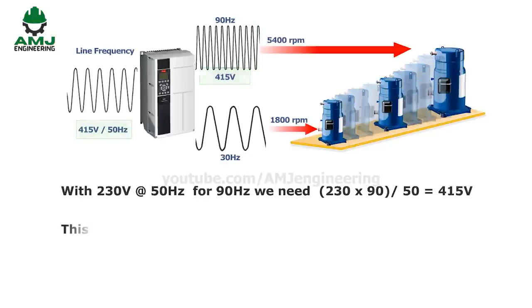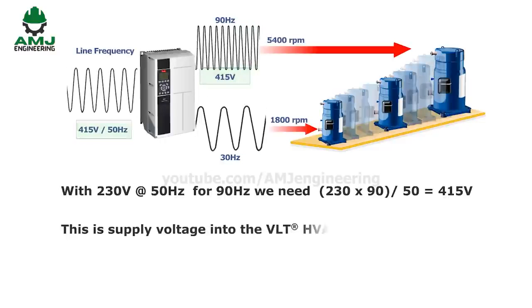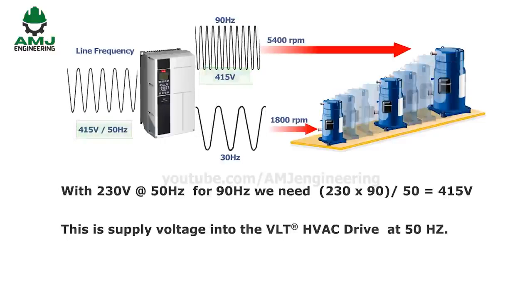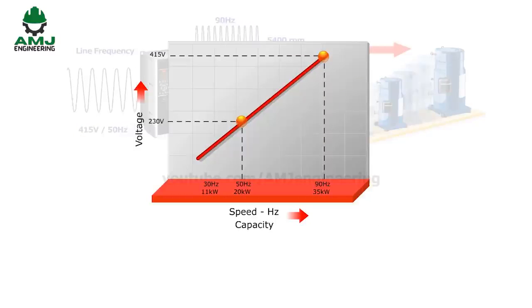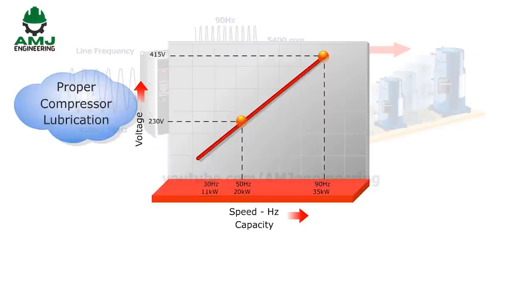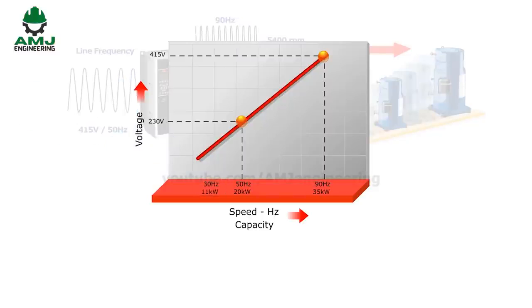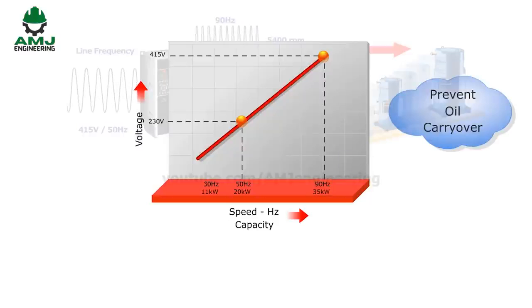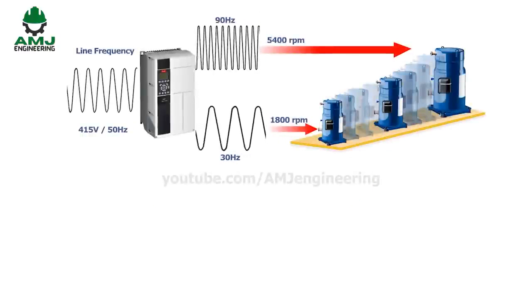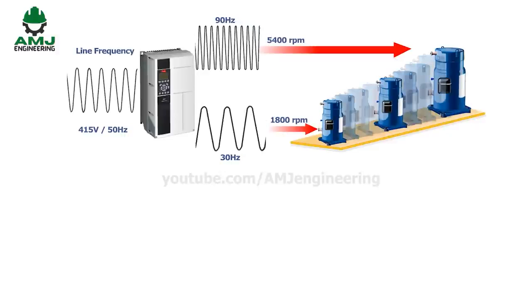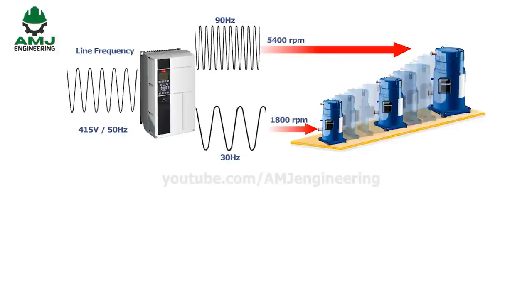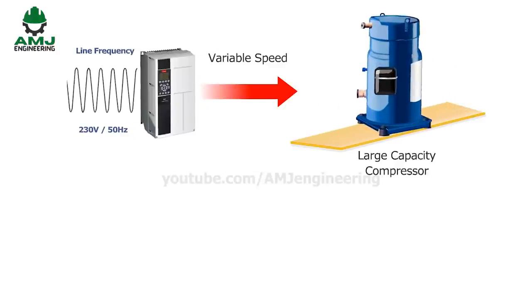415 volts is the supply voltage to the variable frequency drive at 50 Hz. This graph shows the relationship for scroll compressor voltage, capacity, and speeds between 30 and 90 Hz. 30 Hz is the minimum speed required for proper compressor lubrication, while 90 Hz is the maximum speed to prevent oil carryover. So, with the inverter technology, a large capacity compressor operating at variable speed replaces 3 small compressors in a standard solution.